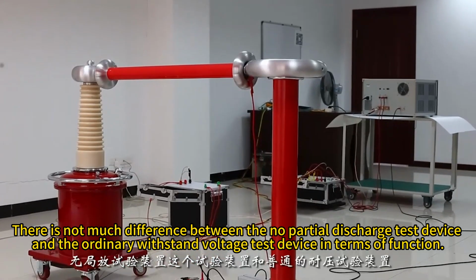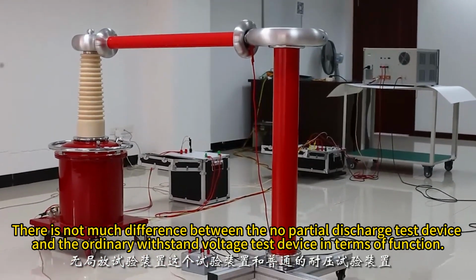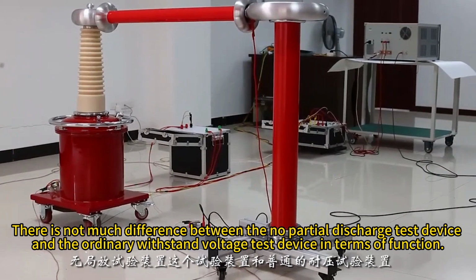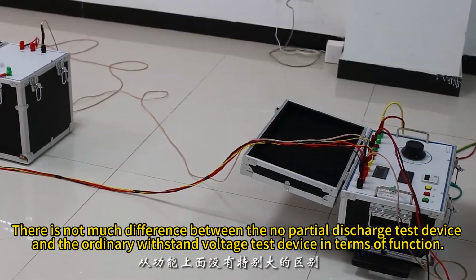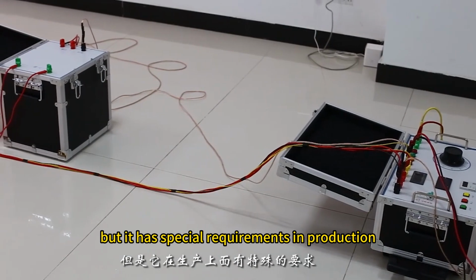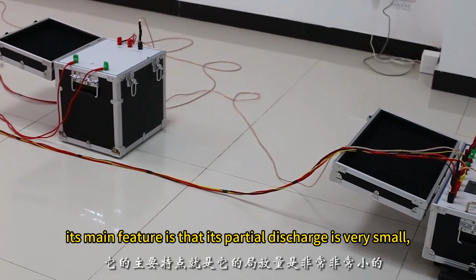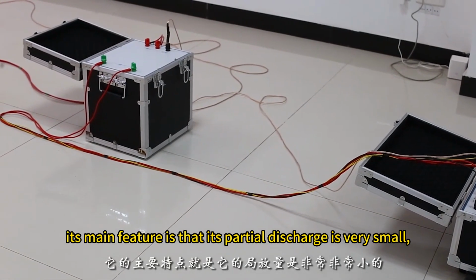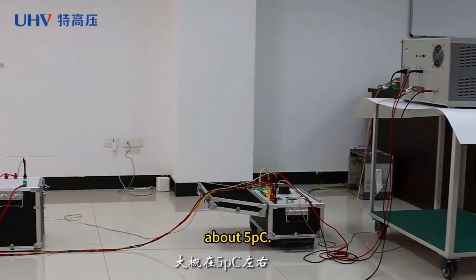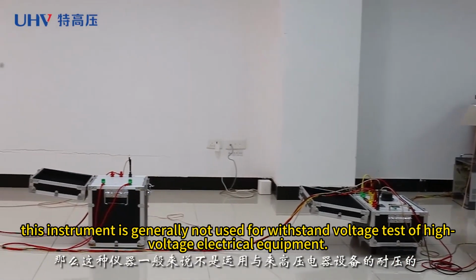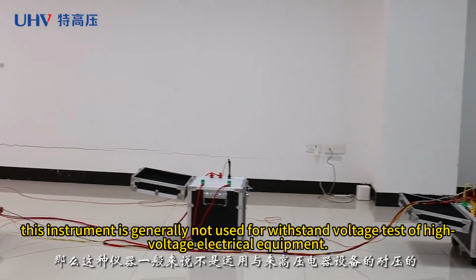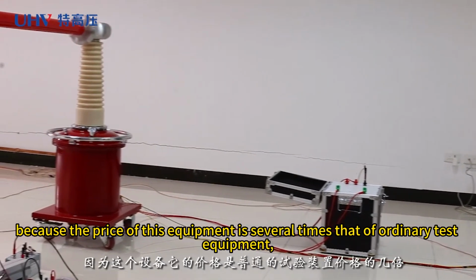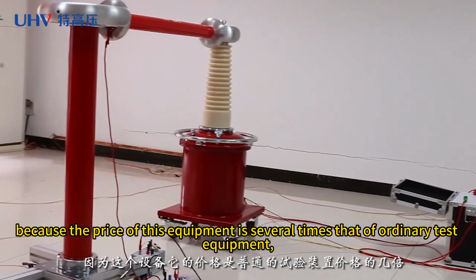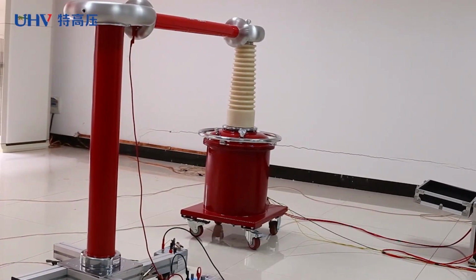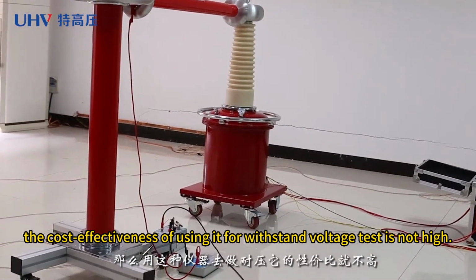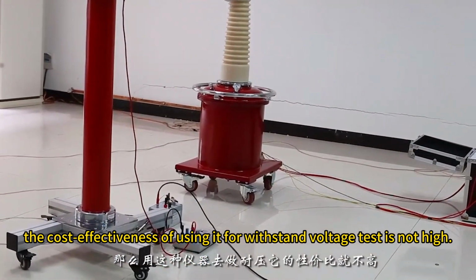There is not much difference between the no partial discharge test device and the ordinary withstand voltage test device in terms of function, but it has special requirements in production. Its main feature is that its partial discharge is very small, about 5 pC. This instrument is generally not used for withstand voltage test of high-voltage electrical equipment, because the price of this equipment is several times that of ordinary test equipment. The cost-effectiveness of using it for withstand voltage test is not high.